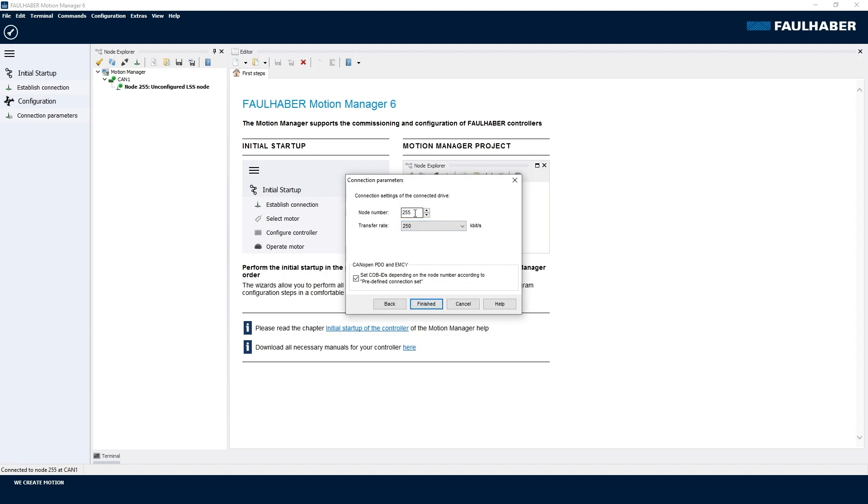Valid node numbers are between 1 and 127, so let's use the 1 here. Please assign a fixed baud rate because in a machine, using auto-negotiation of the communication speeds isn't the best idea. You don't want your drives to negotiate the actual speed at each start of your machine.